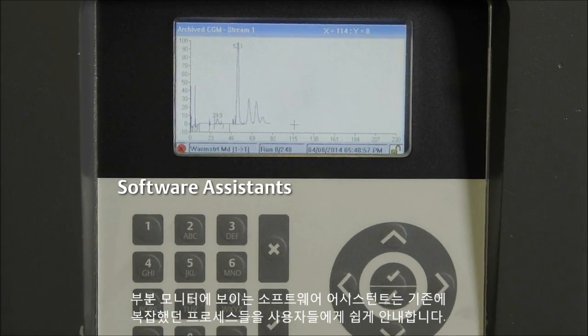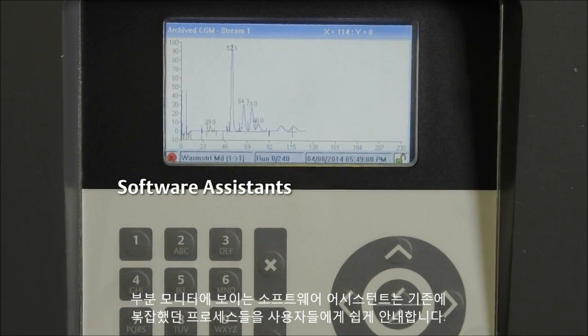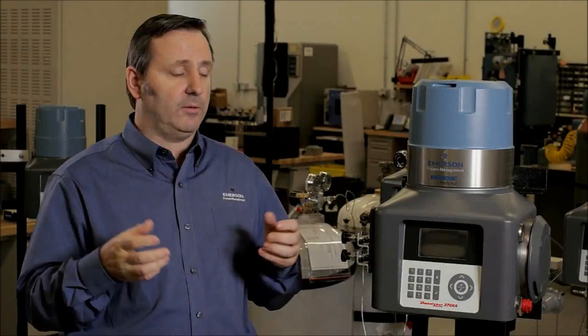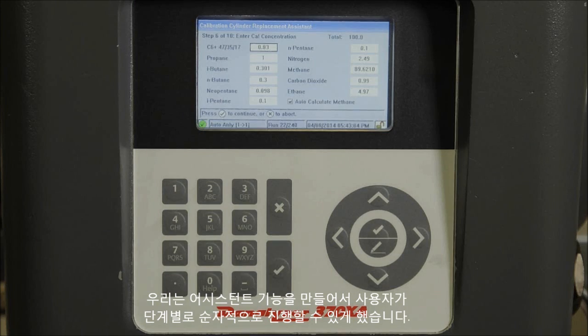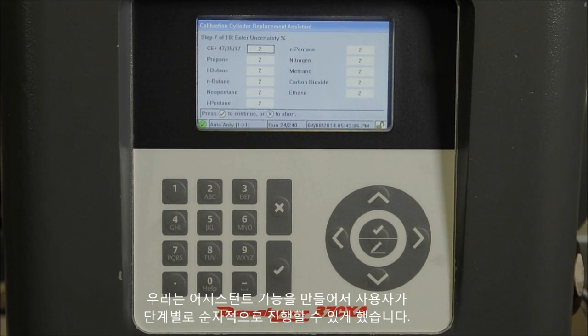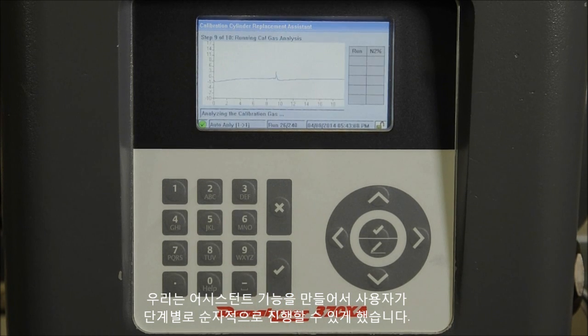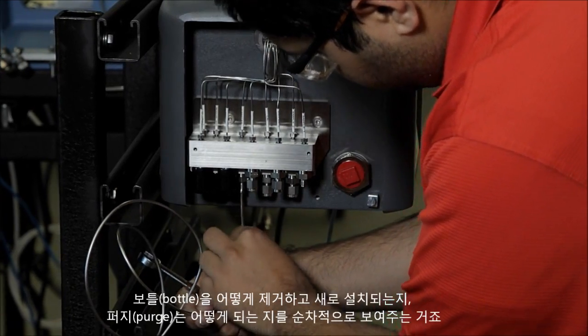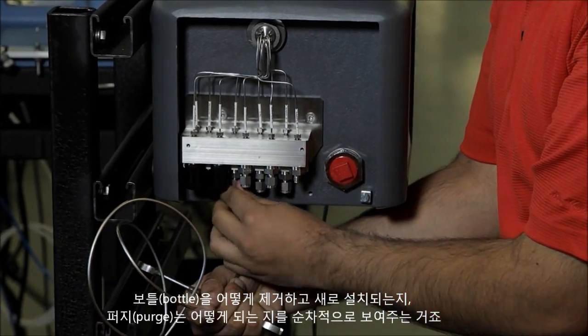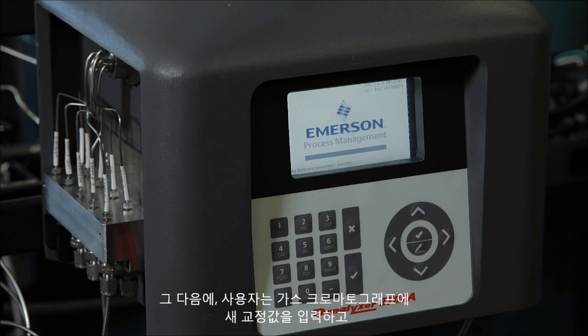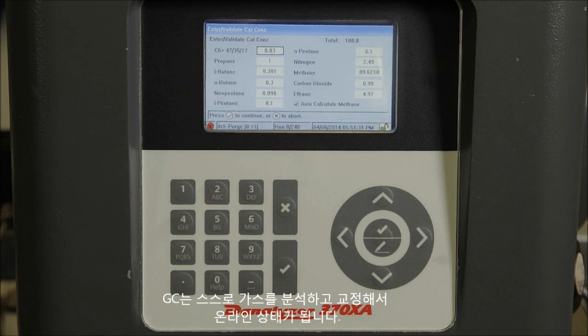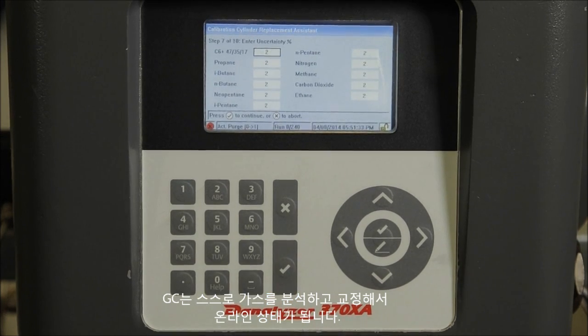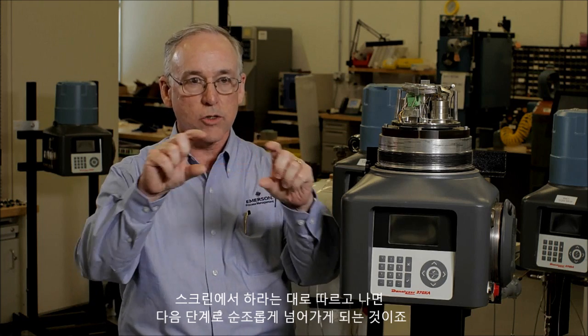Software assistants on the local display steps users through previously complex processes. An example is the change calibration gas assistant. We've created a little assistant that steps the user through the procedure of how to remove the old bottle, put the new bottle on, and purge it. Then the GC prompts the user to enter the new calibration values, analyzes the gas, calibrates, and goes online by itself—so in one set of flows with a set of screens, it tells you what to do, you do it, and then you say, I'm ready for the next thing.